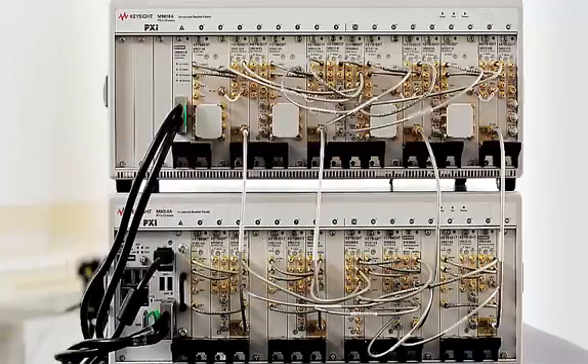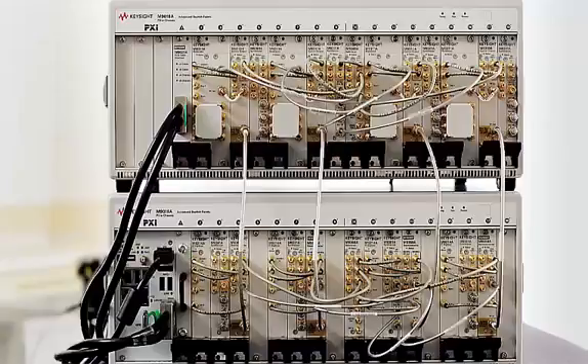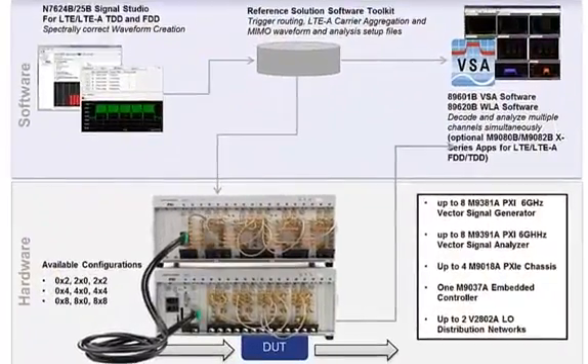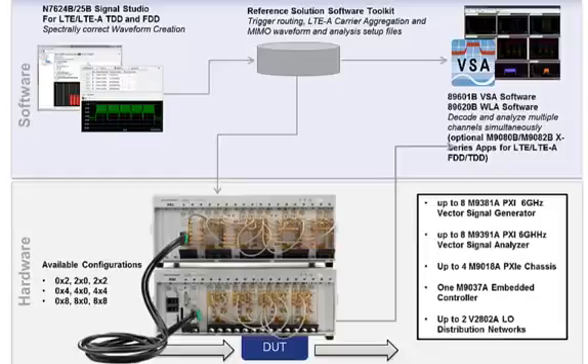Now let's walk through a quick demonstration. In this setup, we will use the multi-channel reference solution to set up for a phase coherent beamforming measurement with time amplitude and phase corrections between channels.